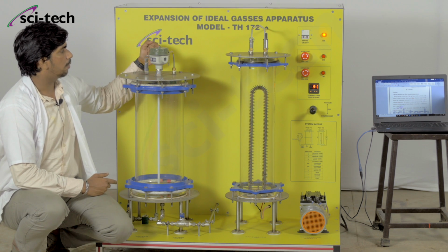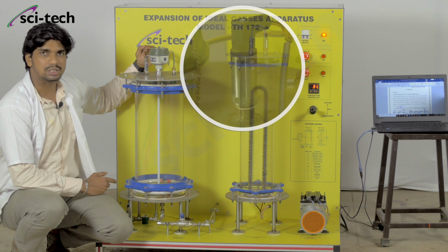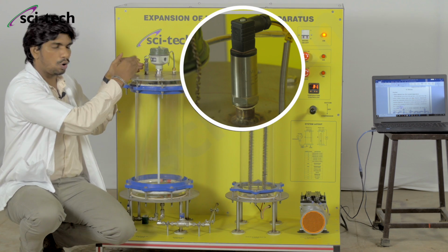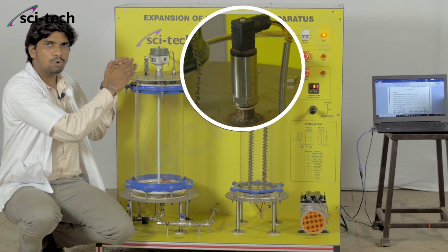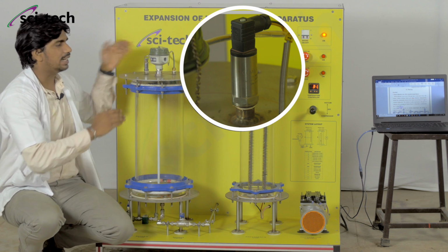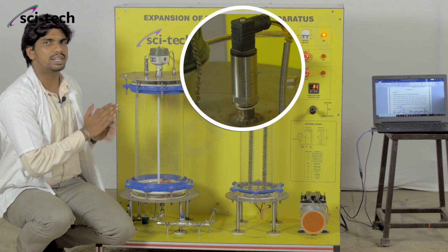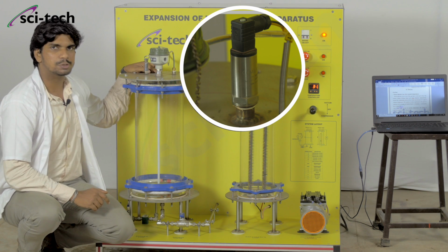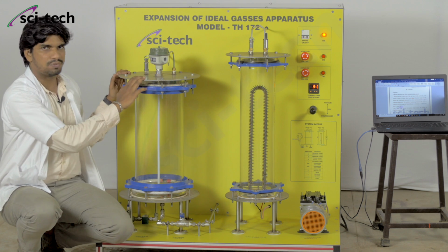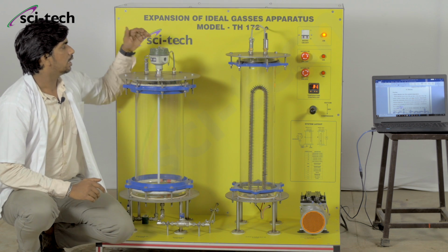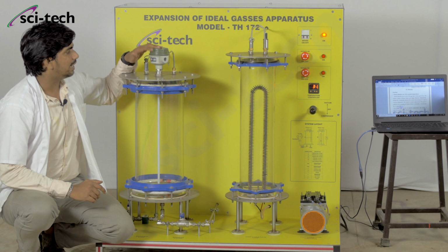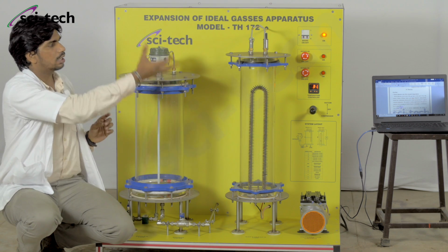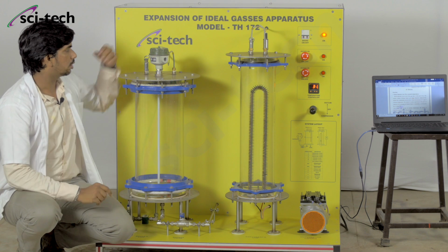Now we will come to the next component, that is our pressure transmitter. This pressure transmitter has a range of 0 to 4 bar gauge pressure and the electric signal output is 4 to 20 milliampere. It is connected with a 1/4-inch BSP threaded coupling on the top flange. This pressure transmitter and the level transmitter send the signal directly to our DAQ model, and this DAQ model directly connects with our application.